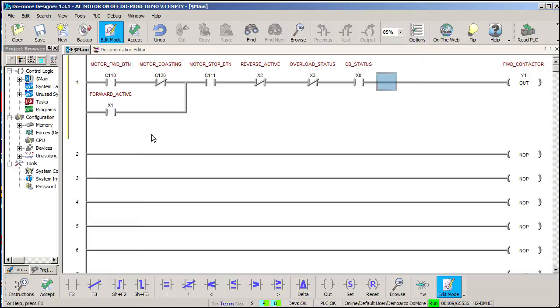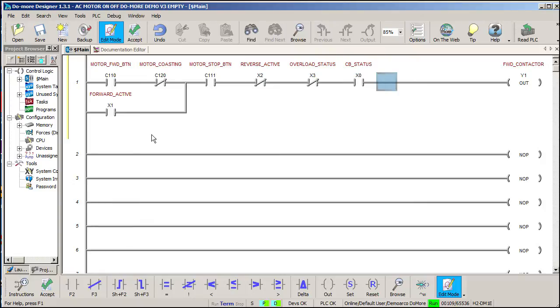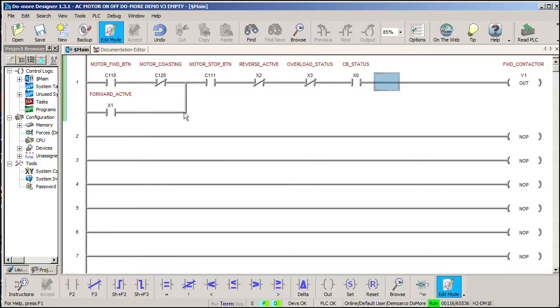So, when the power is applied, the motor will already be enabled and it will jump to life. Normally, we don't want that to happen so adding this contact to prevent the circuit from latching while the power is off is a really important safety feature. And we'll add a comment for that rung.